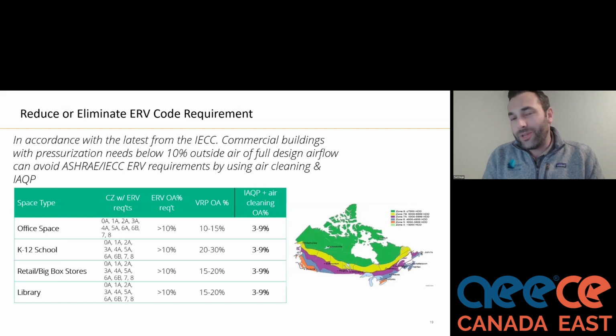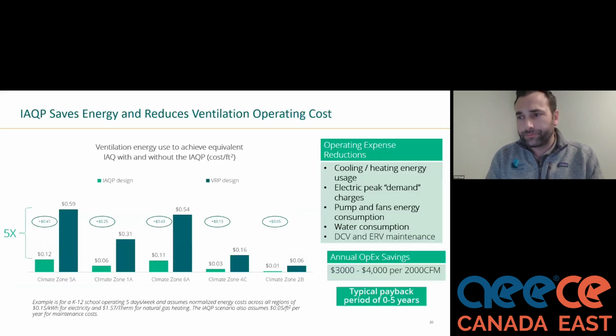I mentioned, and kind of glossed over, eliminating energy recovery requirements. You can reduce or eliminate energy recovery if you're bringing in less than 10% outside air. So with the indoor air quality procedure, what you end up with is pressurization typically driving the minimum required outside air to ensure acceptable indoor air quality. And this is fully allowable with the IAQp and specifically in Canada as well.